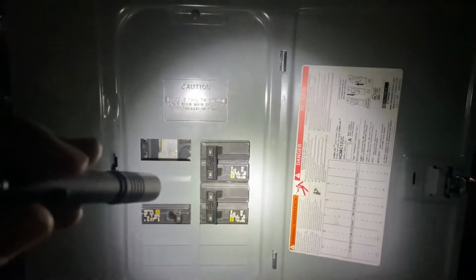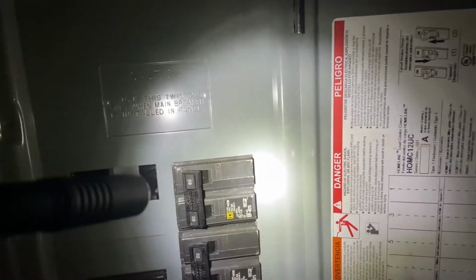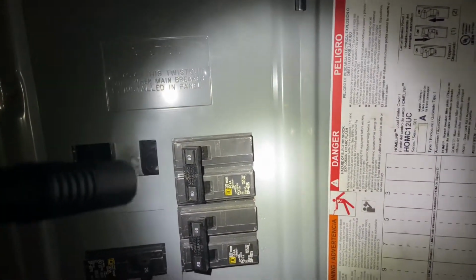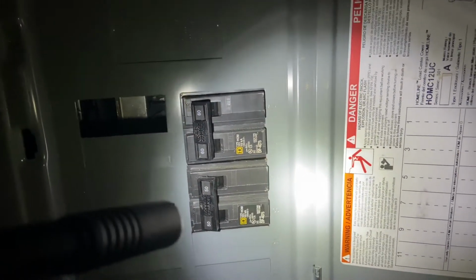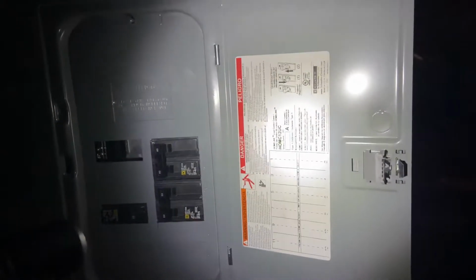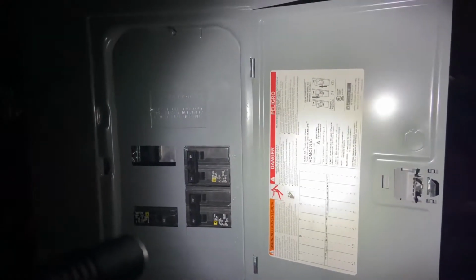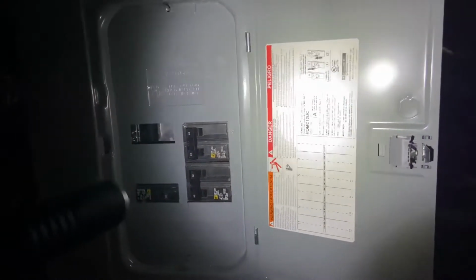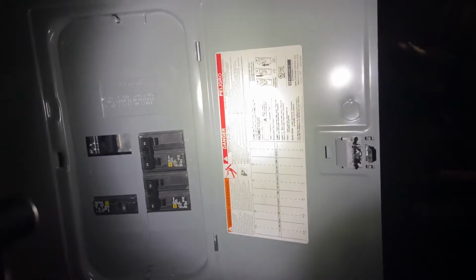So first off, you can see the finished electrical panel right here, right? And we've got our 3 circuits. We've got the 60 amp, which is feeding the blower motor and the first set of heat strips, and the 50 amp feeding the second set of heat strips. Those heat strips will only be on if the heat pump can't keep up. And it's going to have to be into the teens of temperature Fahrenheit before we can do that. So by and large, this won't get used. But when we need it, we'll be glad we have it.